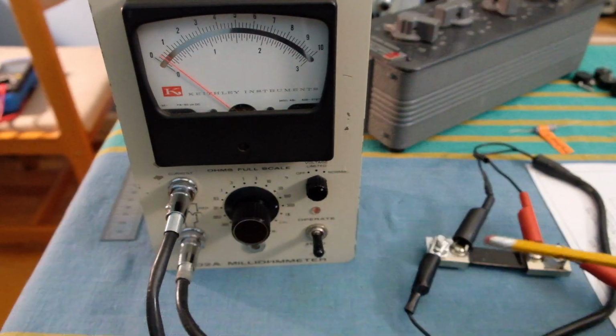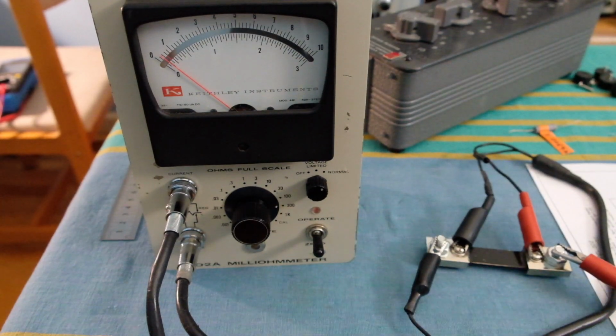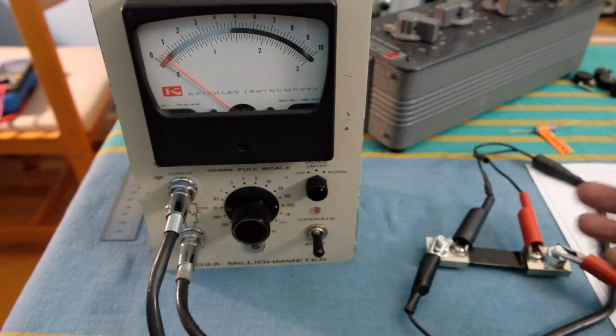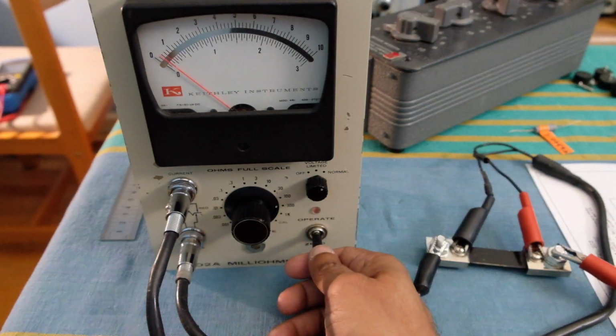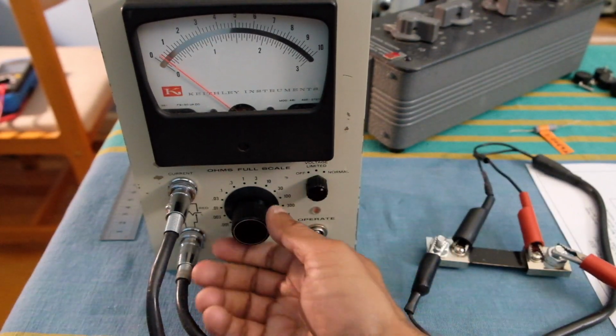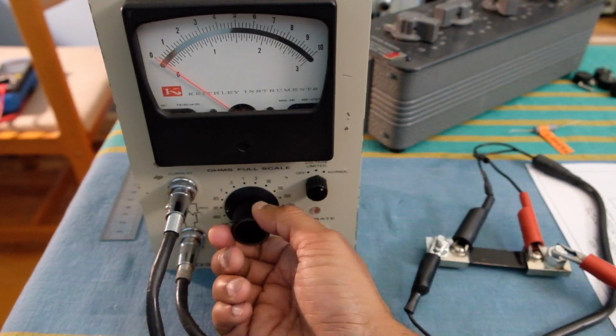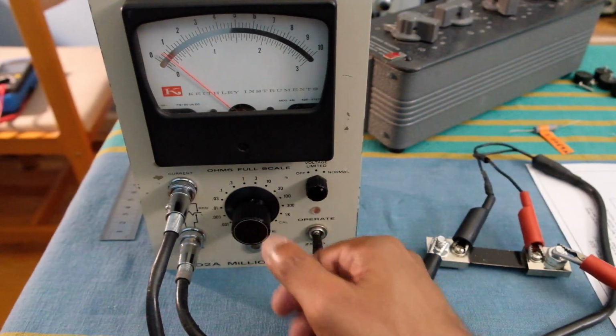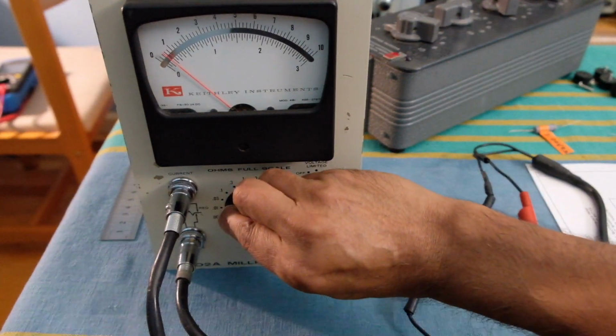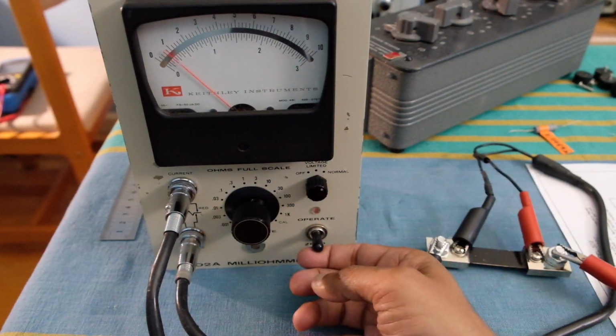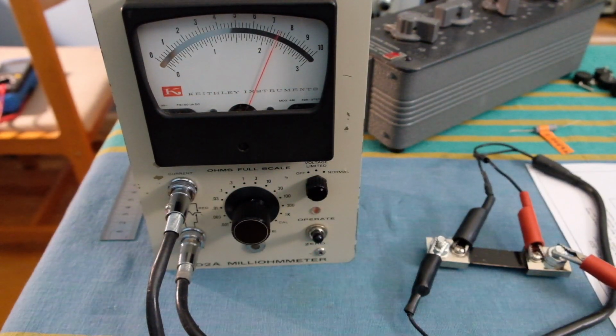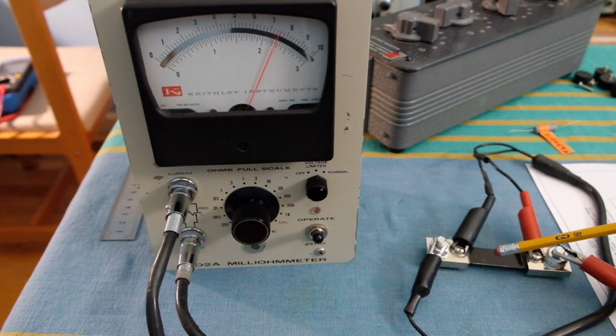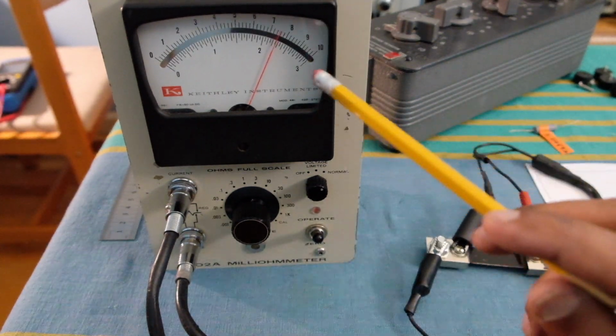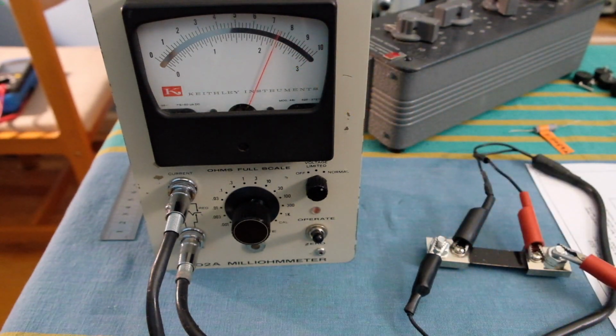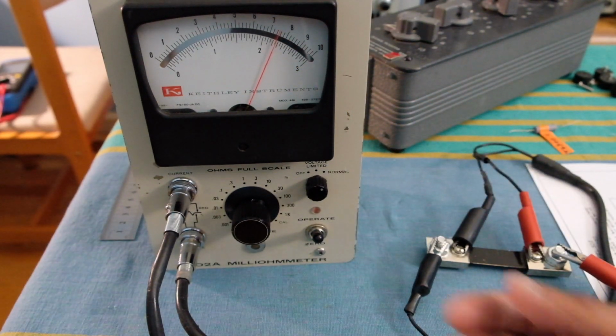Unfortunately, the only way I could check this was to put a large current through it and measure the voltage on it using a regular meter, and that might of course do some heating and so on. But anyway, let's try this one, see what it comes up with. I'm going to the lowest range here, 0.01, 001 that is. And it's 0.74, or is it 750 microohms? I think it's 750 microohms. Yes, 750 microohms is the actual value, and this one is reading around 740 or in that neighborhood. So as you can see, extremely accurate.